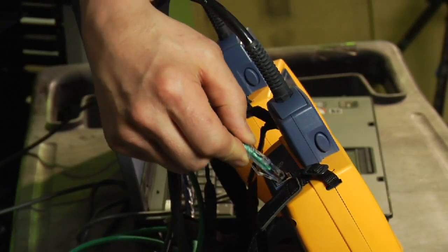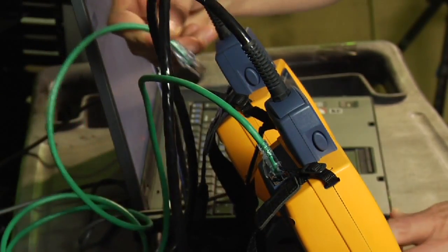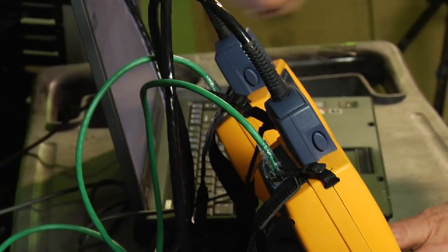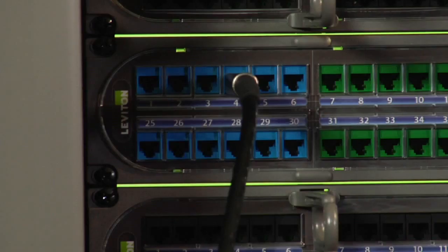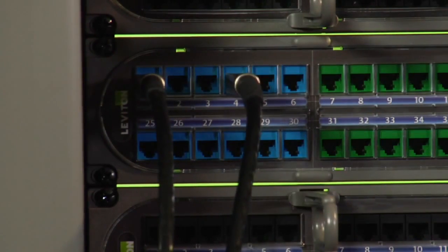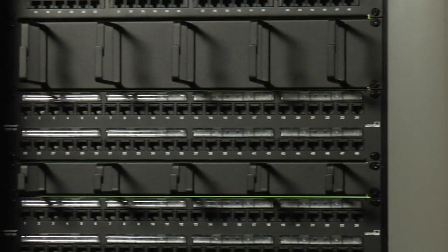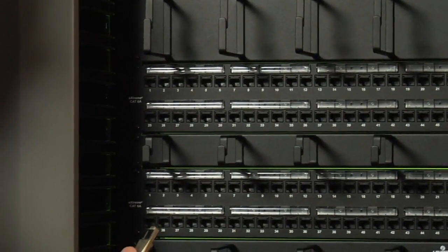Next, we connect the Alien CrossTalk communication modules in the DTX main and remote units using a patch cord. Finally, we take the DTX remote unit and connect it to the first disturber link. You might be wondering, what about the other end of these links? They're not connected to anything. An open at the far end would create signal reflections and make the measurements invalid.